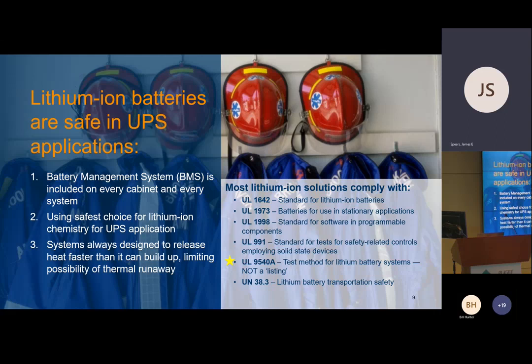The batteries themselves are listed to UL 1642. The battery system in its cabinet is listed to UL 1973, which includes references to UL 1998, the standard for software and programmable components—i.e., the battery management system, which we'll abbreviate BMS, that we already talked about a little bit.